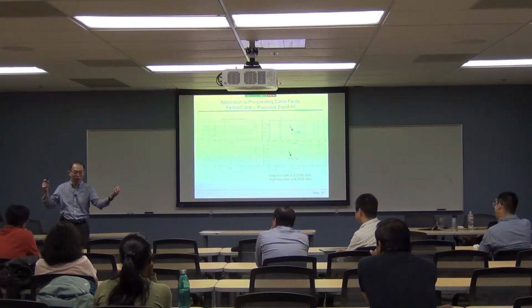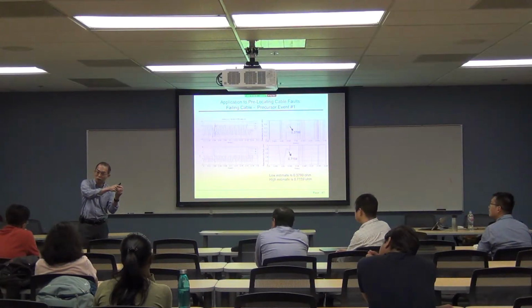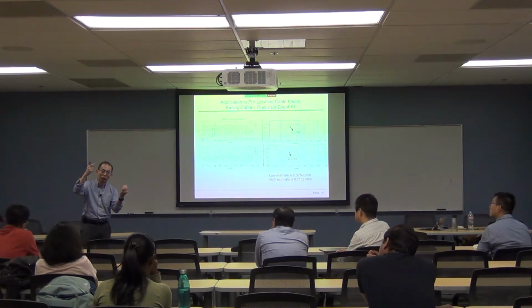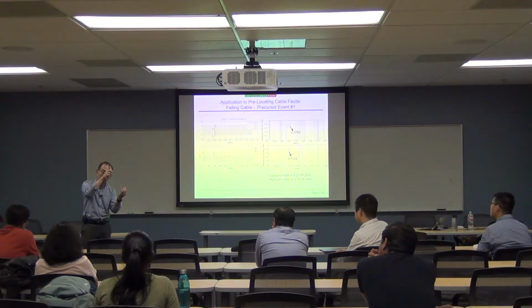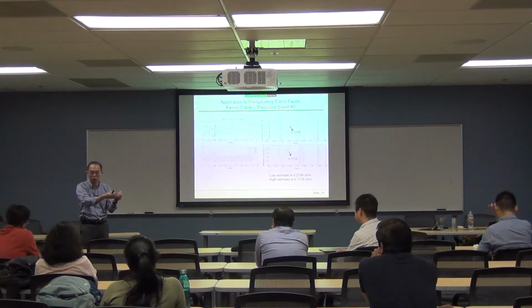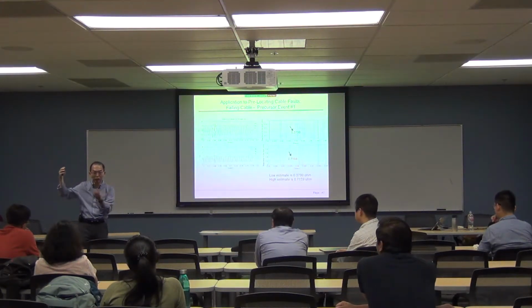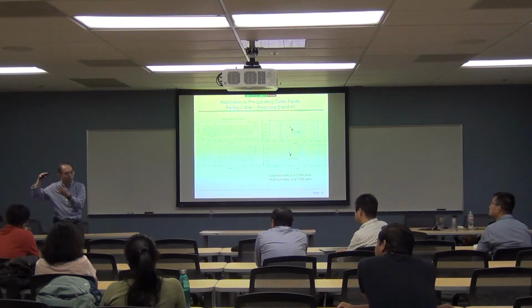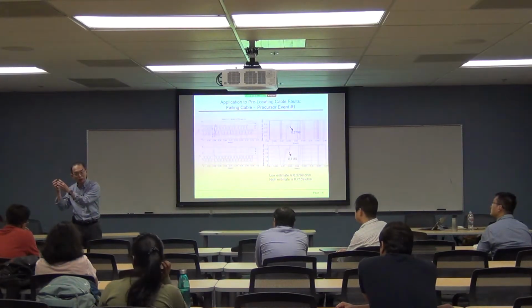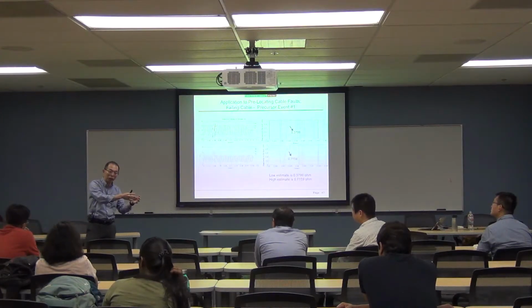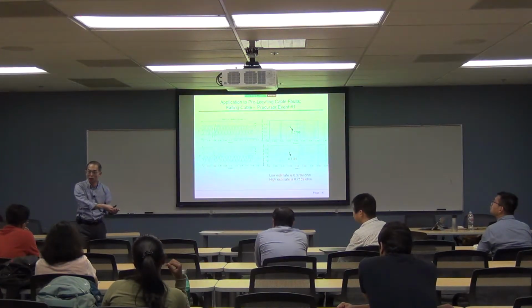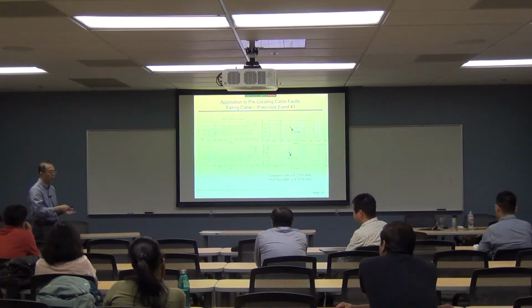So what the monitor sees is the voltage and the current at the substation, not at the fault point. You follow me? So you will have to make an estimation as if you had a monitor in front of the fault, and then estimate what the voltage is at the fault point. That is the arc voltage, okay? And what is that current? Because the current that you see at the substation is the fault current combined with the load current and everything else. So you have an algorithm essentially moving that monitor, dropping it at the fault point. And what do you see right there? Then from there you can estimate the arc voltage.